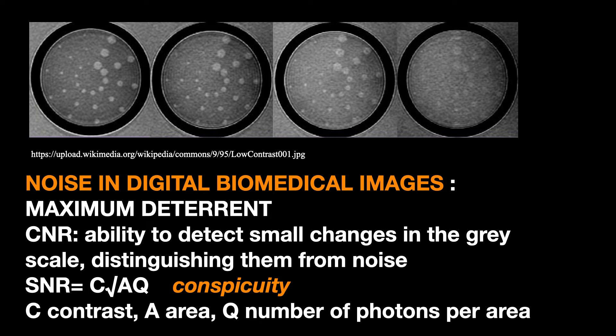Given that signal-to-noise ratio is equal to C (contrast) times the square root of A (area of the object) times Q (photons number per area), we can understand why improving contrast means improving signal-to-noise ratio, which is in fact the more significant parameter to measure the ability to detect an object, called conspicuity.